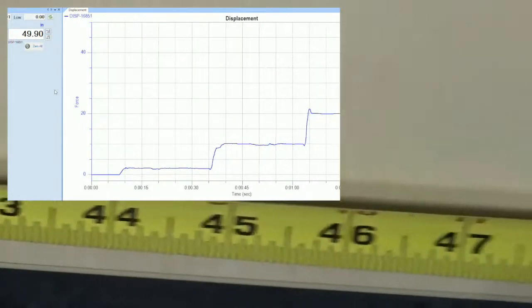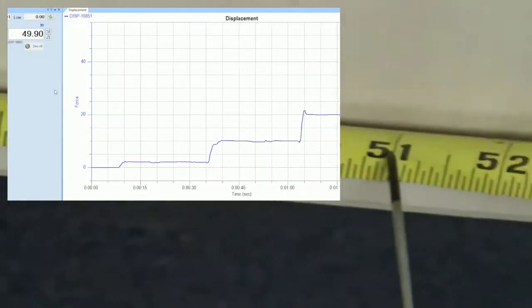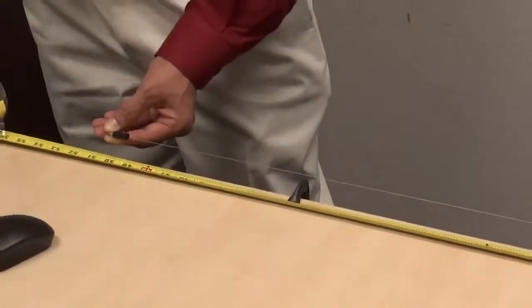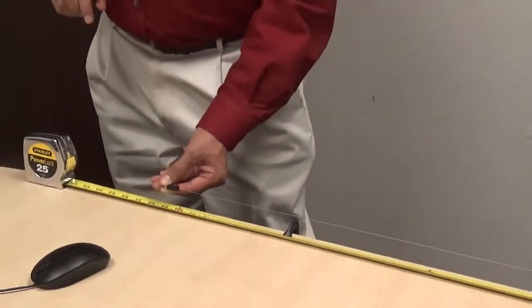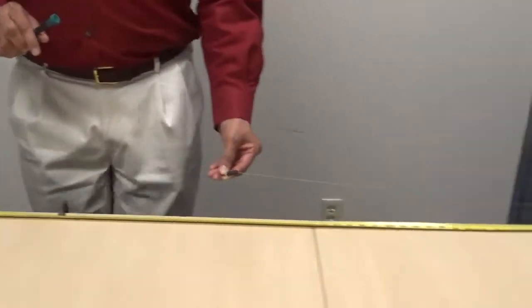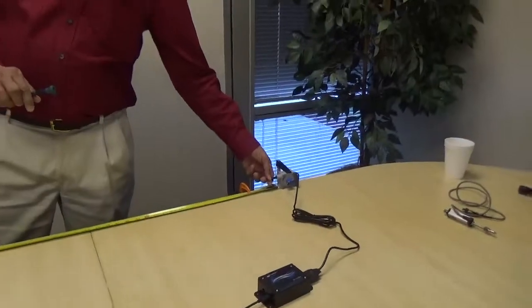And here's 50 inches. It's a 1% device but usually performs much better than 1%. 1% of full scale, so for 50 inches, 1% would be about half an inch, but as you can see it's well within a quarter inch accuracy.